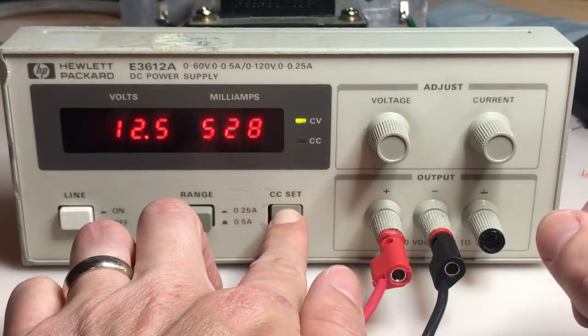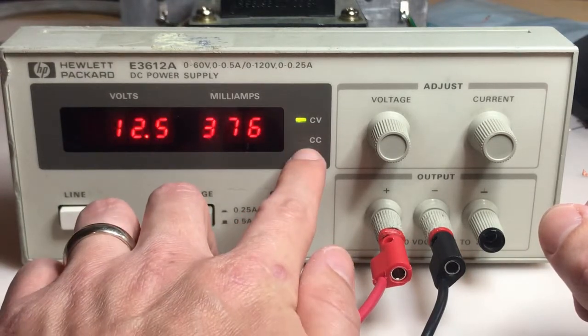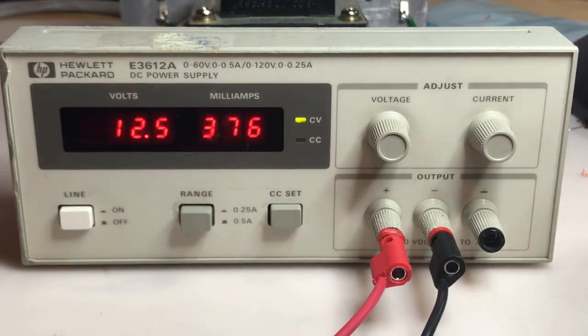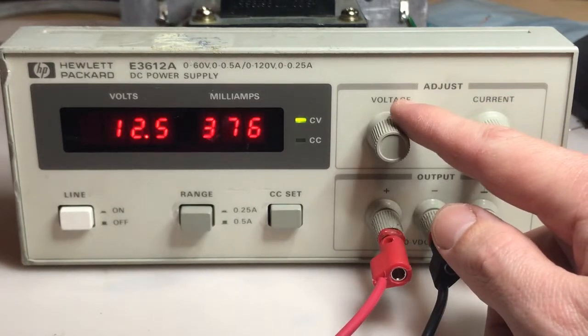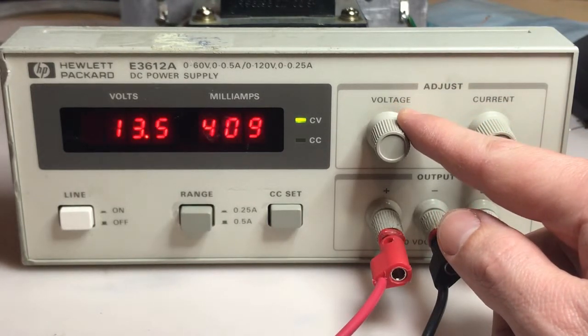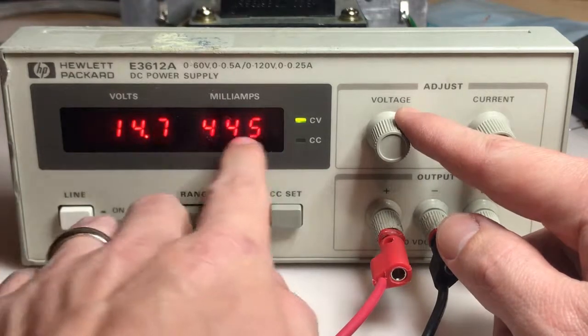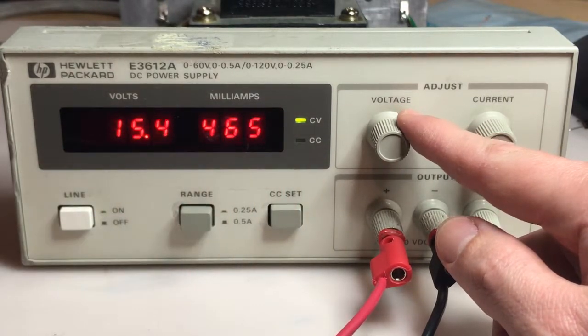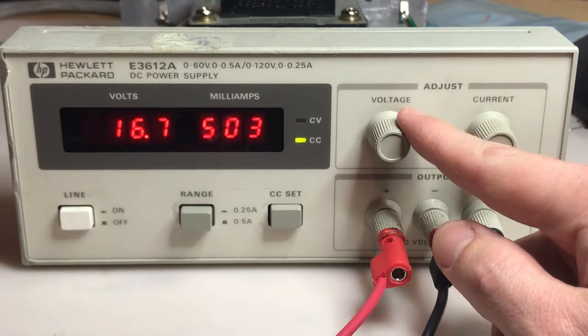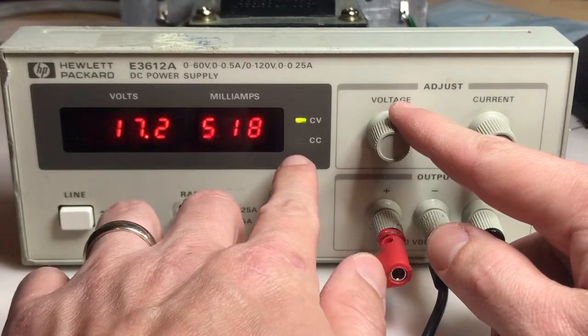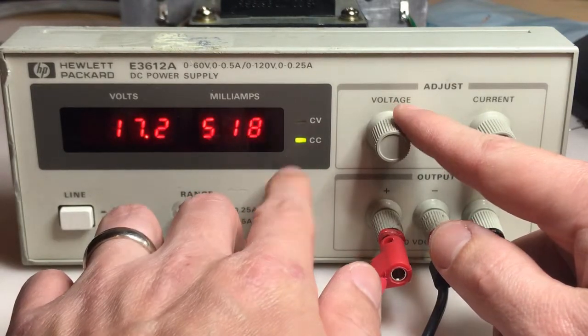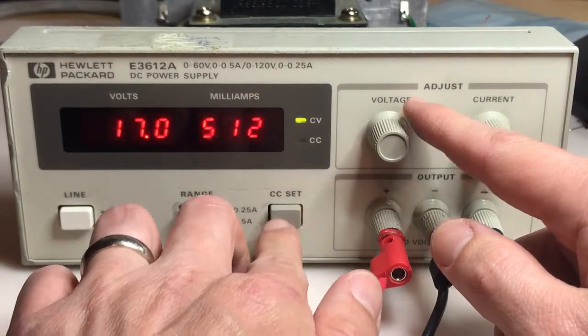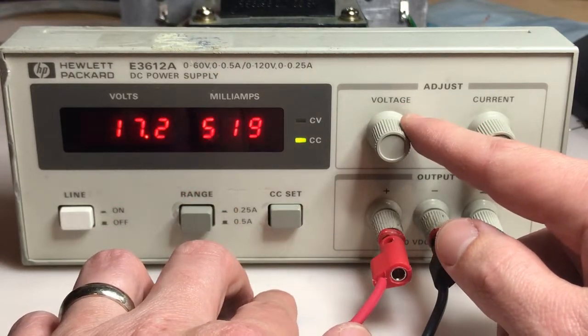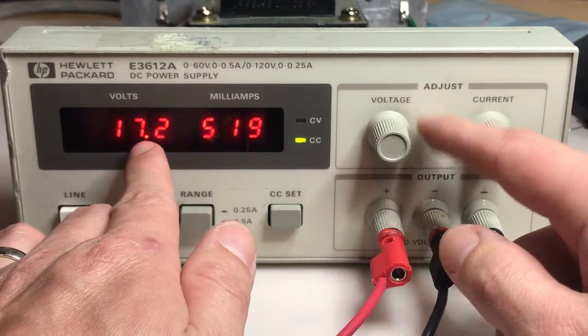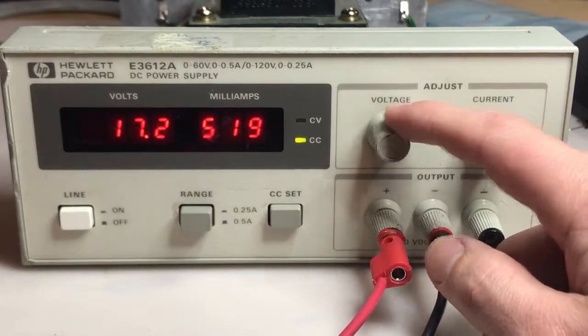At 528 milliamps, we should cross over from constant voltage mode to constant current mode, and that'll keep my voltage constant at that current. So let's see, again at 528 we should cross over to constant current and my voltage will no longer increase. Almost there, we're at 17. Okay, so we're there. So it happens at 520. Yeah, and I can turn it all I want, the voltage will not increase past 17.2.